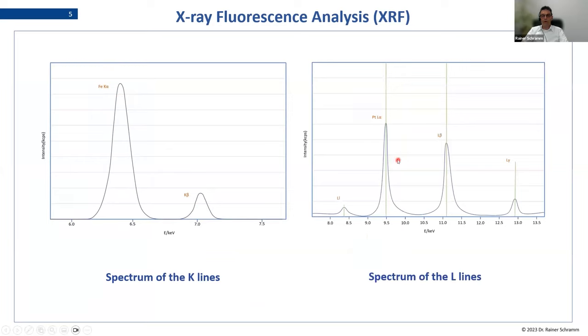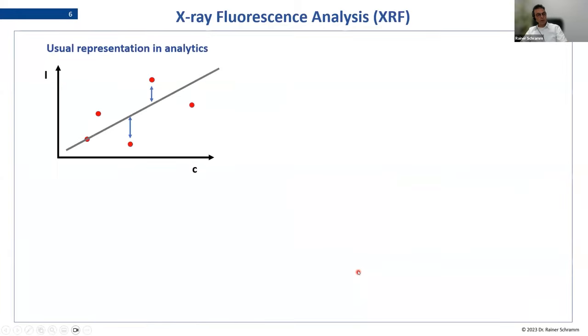A typical spectrum will look like this: for iron you would see a K alpha line and a K beta line, with a difference of around a factor of five between the lines. For an L pattern, like platinum, you see four peaks at different heights which define a typical L pattern. The intensity in energy-dispersive XRF comes from the area (surface) of the peak, while in wavelength-dispersive XRF it comes from the height of the peak. Both are called intensity, and for both all following models are the same — there is no difference between the two technologies.